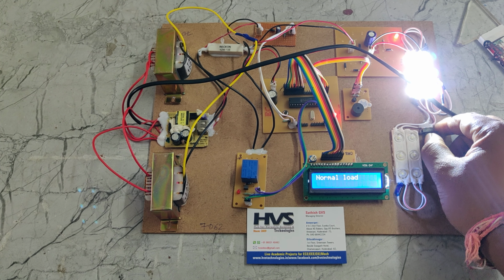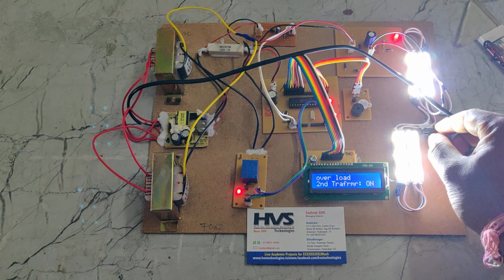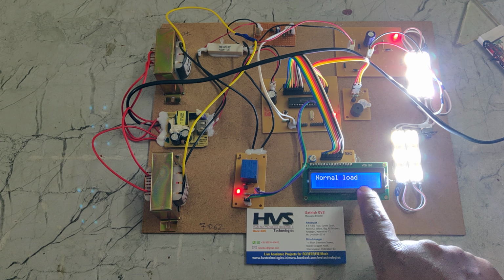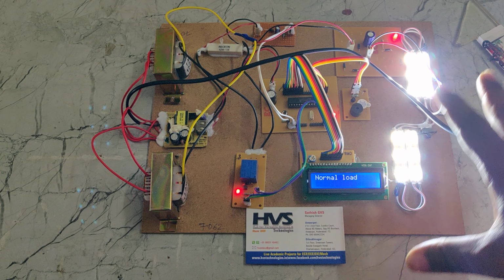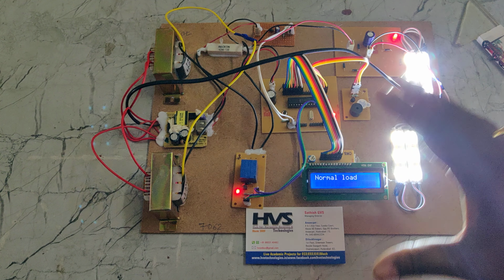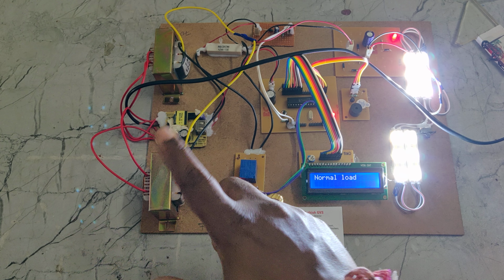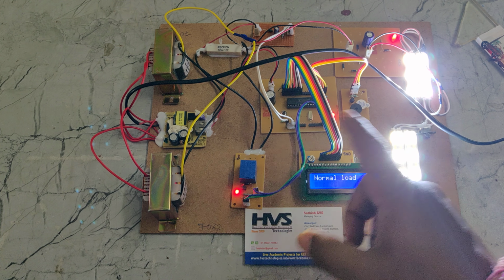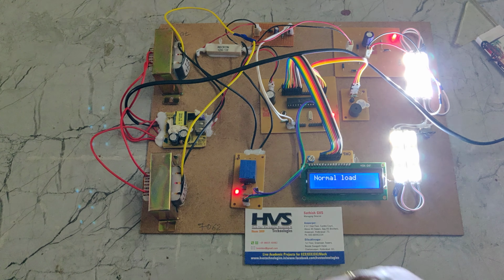When we connect the secondary load, the system measures the overload and switches the second transformer on, so the load is shared between the two transformers connected in parallel, which is the normal condition for load sharing.